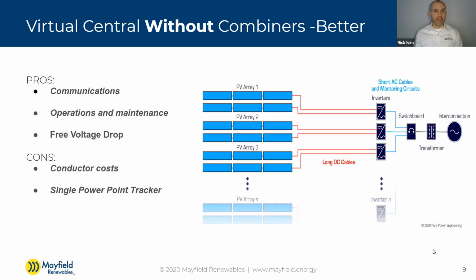Also, if you ever have to replace inverters, these sites often get muddy and don't always have good roads or stone paths leading to inverter locations when they're spread throughout the array. But when all the inverters are at a central location, it's very likely you've got a good access road there, so you can drive vans or trucks right up to it. It's a lot easier to swap out inverters or equipment without driving trucks that tend to get stuck out in the fields when you have to drive around to different locations.